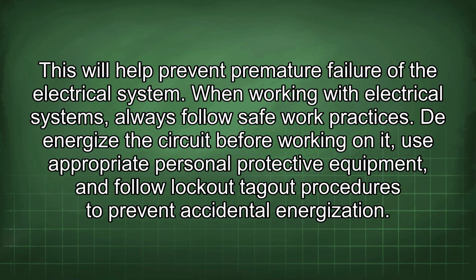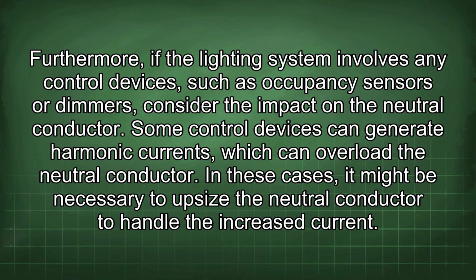When working with electrical systems, always follow safe work practices. De-energize the circuit before working on it, use appropriate personal protective equipment, and follow lockout-tagout procedures to prevent accidental energization. Furthermore, if the lighting system involves any control devices, such as occupancy sensors or dimmers, consider the impact on the neutral conductor. Some control devices can generate harmonic currents, which can overload the neutral conductor. In these cases, it might be necessary to upsize the neutral conductor to handle the increased current.